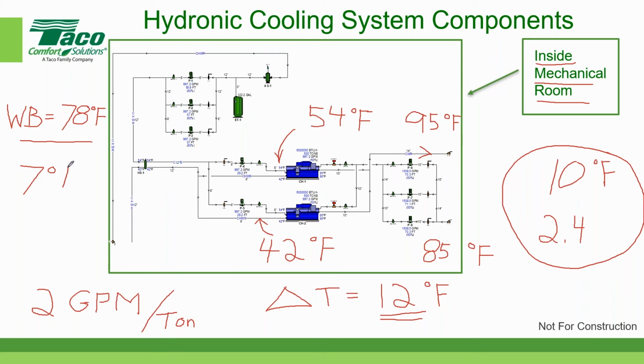Okay, so here's where the fun starts. You can get a lower approach temperature. You can't change the wet bulb. That's a weather condition, part of the physics of the universe, at least as we know it on Earth. You can't manipulate the weather, but you can change the approach temperature. But if you shrink the approach so that you have cooler water going back to your chillers, you have to have a physically larger cooling tower. You have to have more surface area, and you have to evaporate more water in order to get the approach closest. So the closer you get to 78 degrees, the bigger the cooling tower has to be.